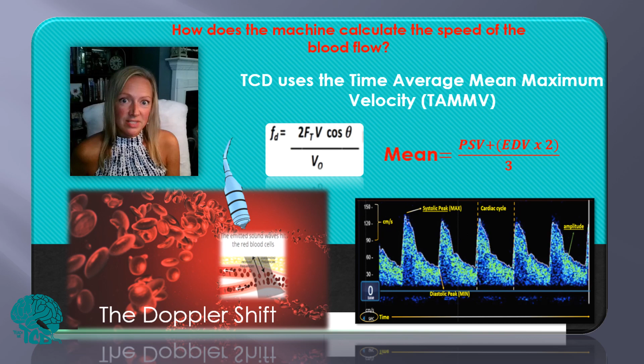TCD mean flow velocities are very important to always keep your eye on when scanning. You're looking for those high mean velocities. However, there is another parameter to watch while scanning, and that is your pulsatility index. Your pulsatility index, or your PI, will determine the resistiveness of the vessel. Now, a normal PI, as you can see on the left here, the 0.93, this is what your waveform will look like if your PI is in the normal range.